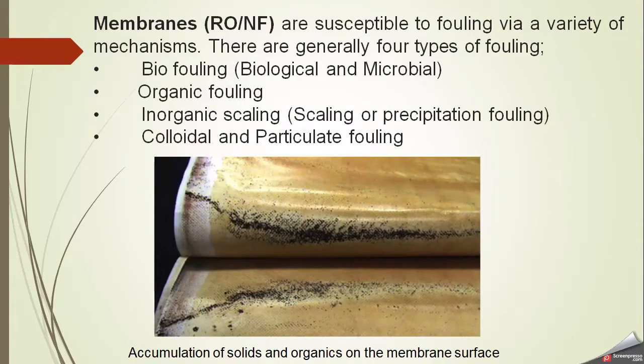Membranes, whether reverse osmosis or nanofiltration, are susceptible to fouling via different mechanisms. We normally categorize these foulings into four categories: biofouling (biological or microbial), organic fouling, inorganic scaling, and colloidal and particulate fouling. This picture, taken from a book, shows accumulation of solids and organics on the membrane surface.